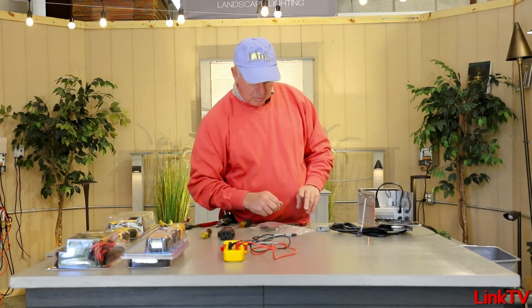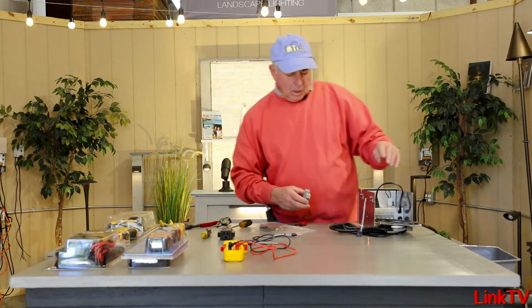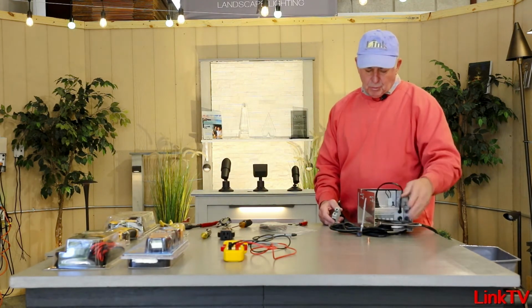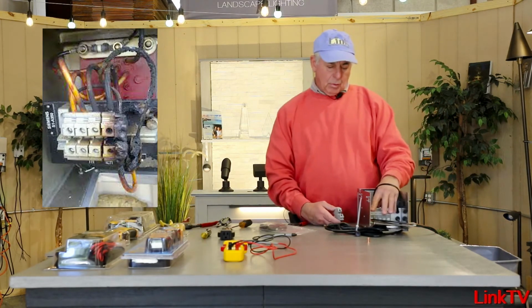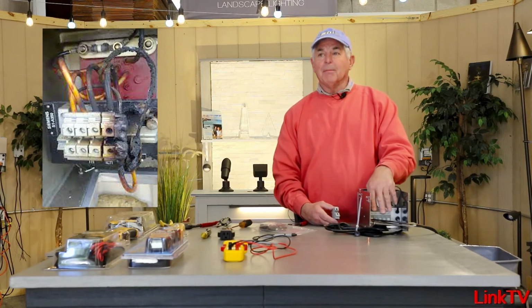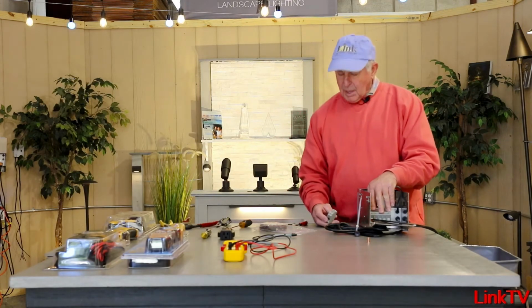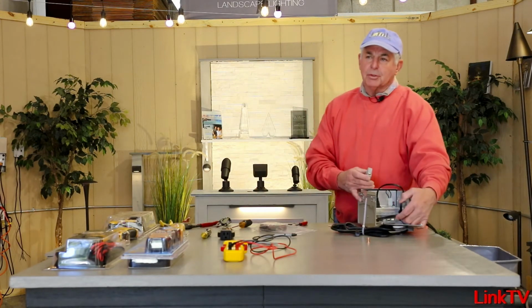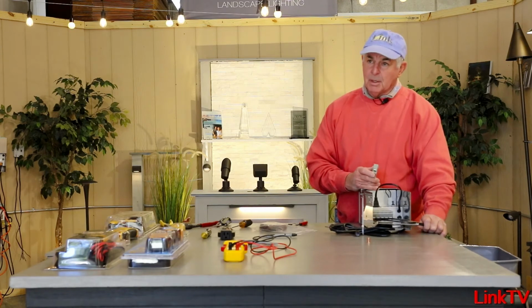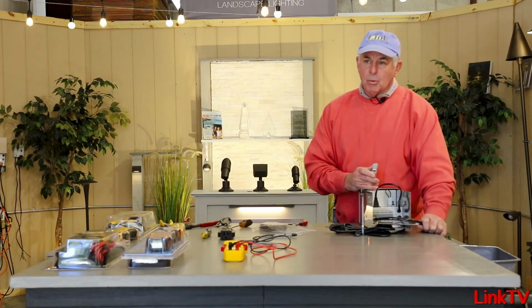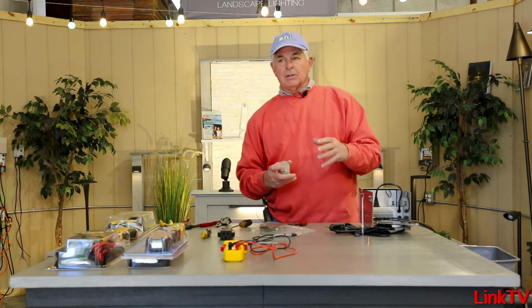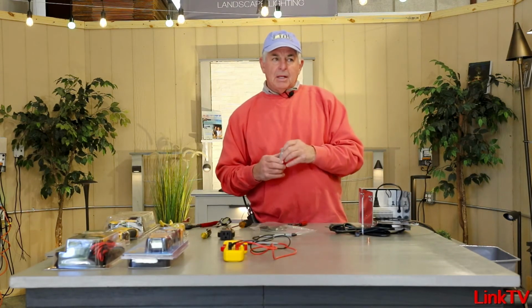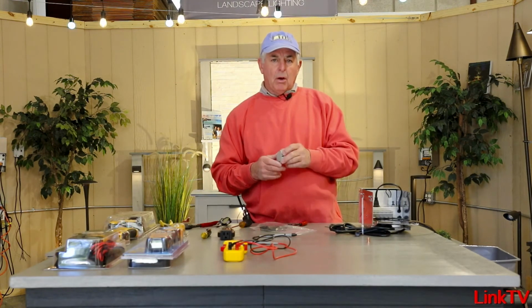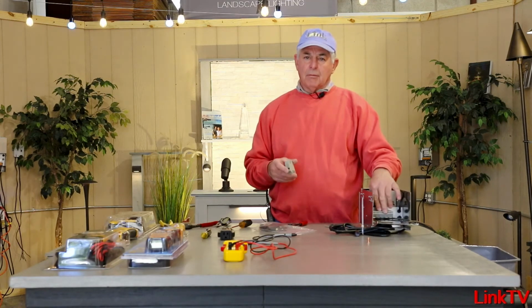Now I've got two more things to go over. You've probably seen a transformer where the terminal blocks are melted. Guys will call and say it's a bad transformer—no, it wasn't. What happened was they weren't getting a good purchase or clamp on the wires, leaving stray hairs. When the transformer comes on, particularly in the halogen days, the wires got pretty warm under normal load, and that warming and cooling starts an annealing process. They loosen up, and when they loosen up, they arc. When they arc, it catches fire, particularly in a low voltage environment.